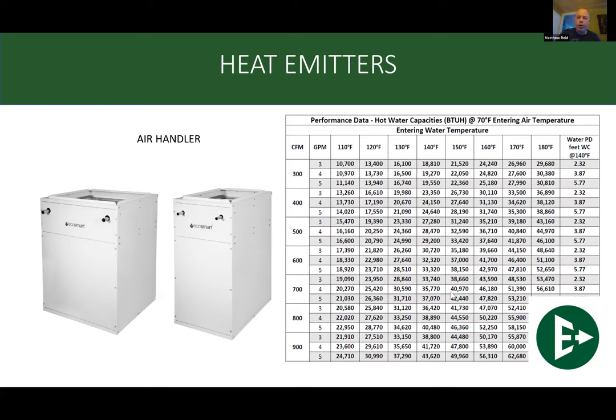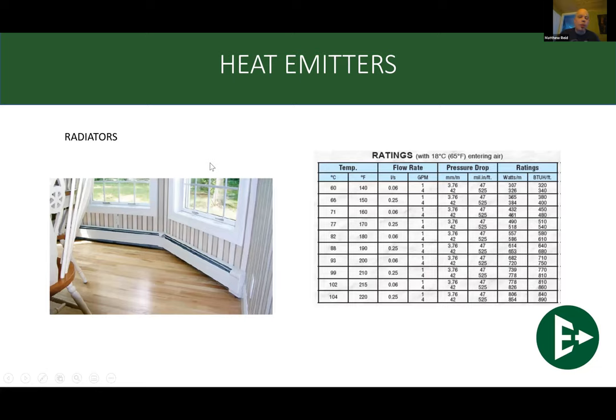So again, once you have your heat loss, you figure out how to get that heat into the home. Now with an air handler, we're talking about whole home, but maybe we are not talking about air handlers. Maybe we're talking about baseboards. You want to do it room by room. Let's look back to this room. This room had a heat loss of about 600 BTUs. So, 600 BTUs for this room.